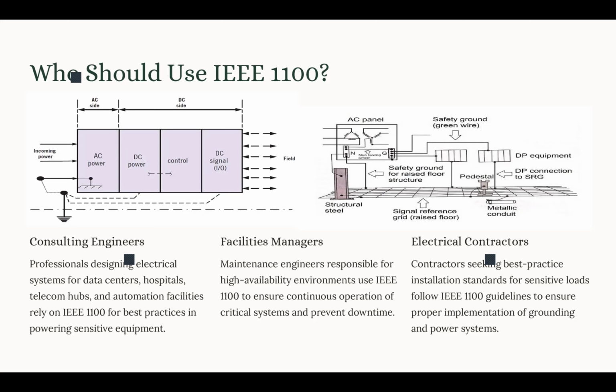Now, IEEE 1100 provides them with engineering best practices beyond safety, so they can make sure they have power quality, noise suppression, and system uptime. If there is a design failure as the result of ignoring IEEE 1100, that can lead to data loss or production downtime, or, in medical systems and healthcare environments, even life-threatening failures. So the standard IEEE 1100 is very important. It is essential for their design, basically providing a verification checklist when dealing with sensitive electronic equipment.